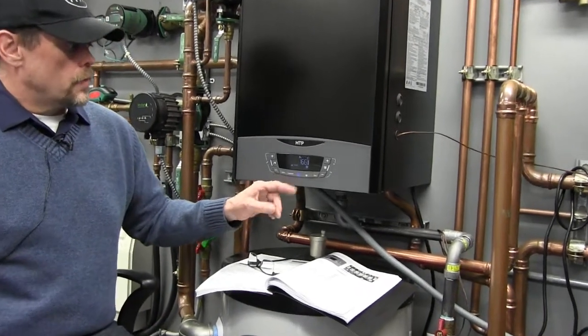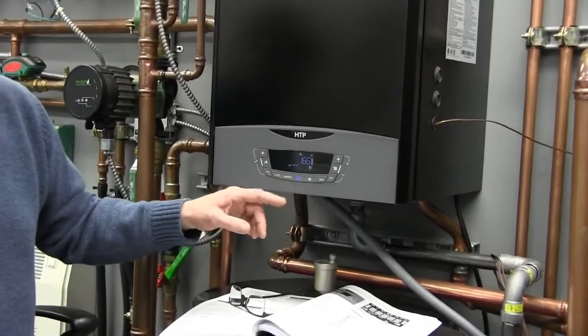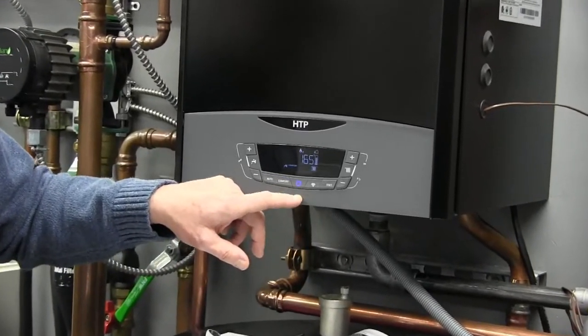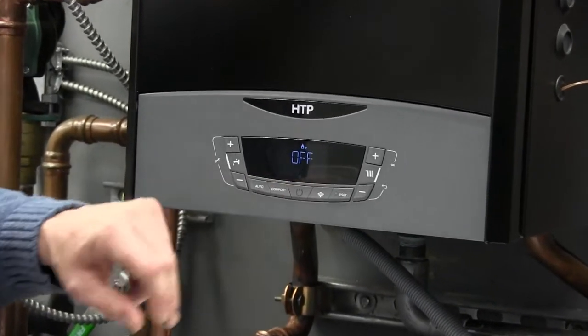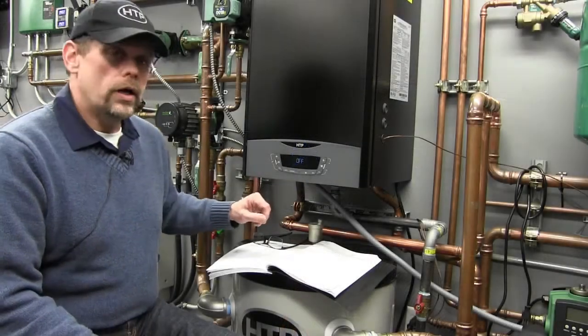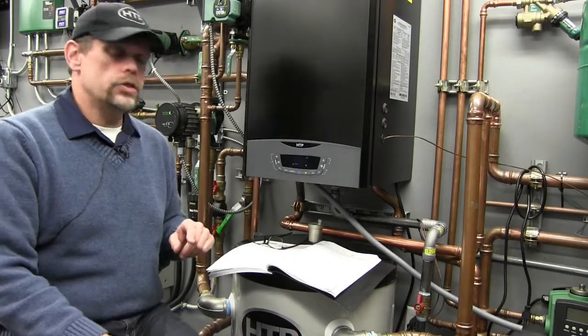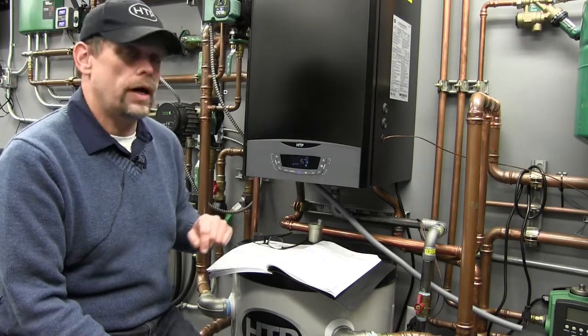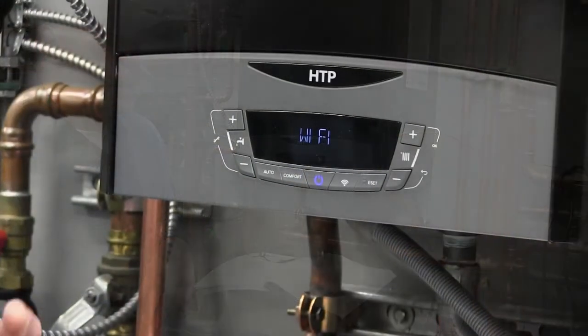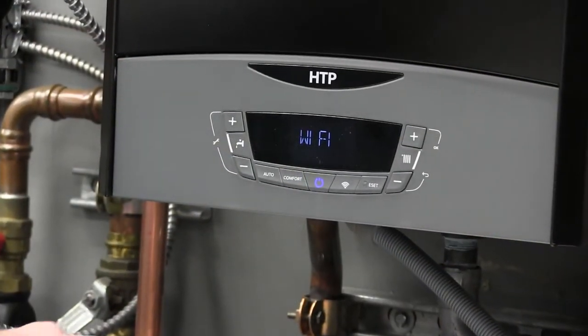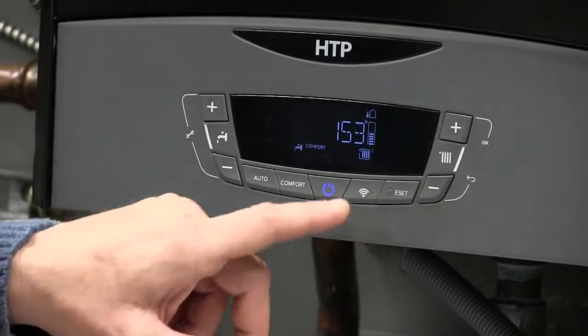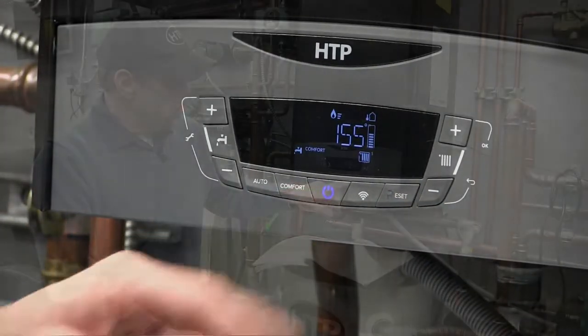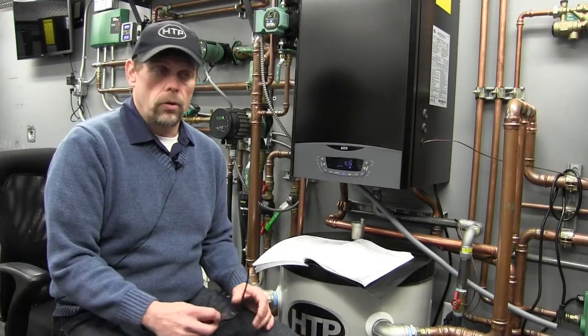The next button is the on and off button. Obviously, when it's backlit, there's power to it. If we shut the power off, okay, let's turn that back on. And as we move left to right, the next button we see is the Wi-Fi button. Another video that you can access for that, but we'll move on. And the next button that we see is the reset button. The reset button, of course, if the boiler or burner should have a lockout, a safety lockout, and need to be reset, that is where we're going to go and do that.